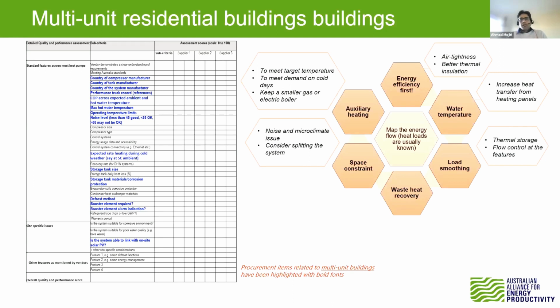And the auxiliary heating, it was very interesting to see that ESW is utilizing the on-site PV as extra heating to raise the temperature inside the tank. If we require a higher temperature beyond the capability of the heat pump, we can use auxiliary heating for different purposes. For example, one is to suppress Legionella growing in the tank. Another aspect that requires auxiliary heaters, sometimes called backup heaters, is during very cold conditions, when the thermal load is high and the COP of the heat pump is relatively lower, and the auxiliary heater can come in and compensate for that.